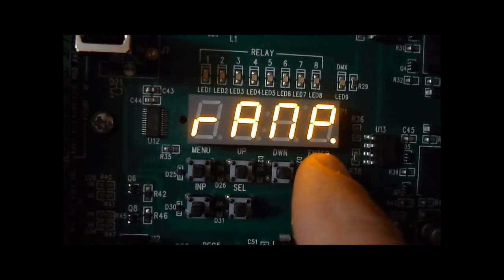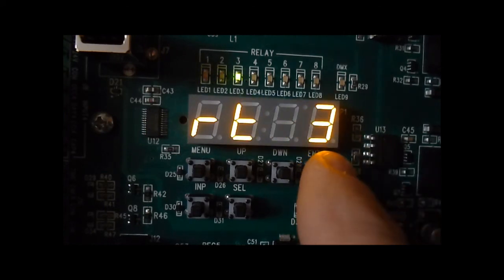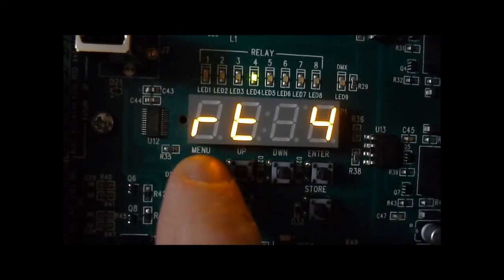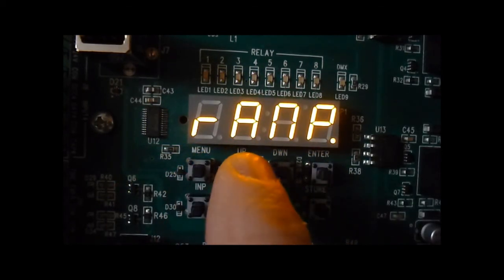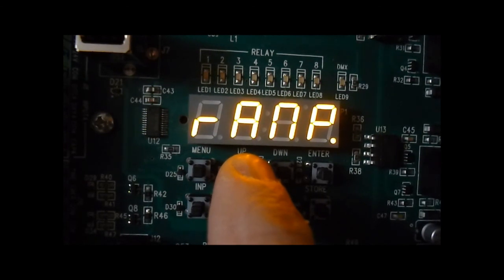The next menu item is a ramp test. Press enter. The unit will chase through all the zones on the relay panel, ramping up each time. Just press menu to exit, and any relay settings that were being controlled by other inputs will return back to control to those inputs.